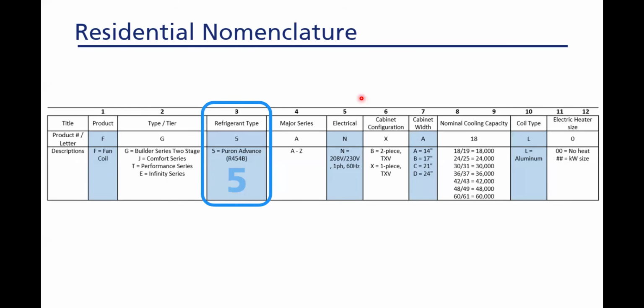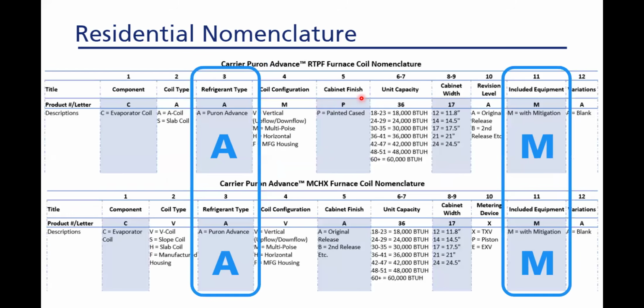All the equipment, as you would anticipate, has a part number change in it somewhere to let you know you have the new refrigerant. This is a simple fan coil. Right? I won't go through every single piece of equipment with you. Just know there's a digit that changes on everything. Rooftop, like whatever, it's a guide digit that changes. The one that's a little weird is a furnace evaporator coil because it actually has 2 digits different in there. One of them tells you that you have the new refrigerant. In this case, the third digit switches to an A to tell us that we have Puron Advance R-454B.